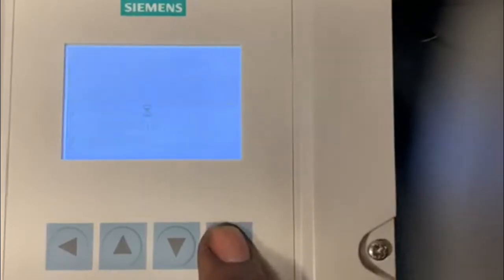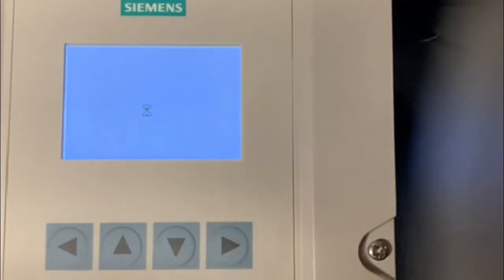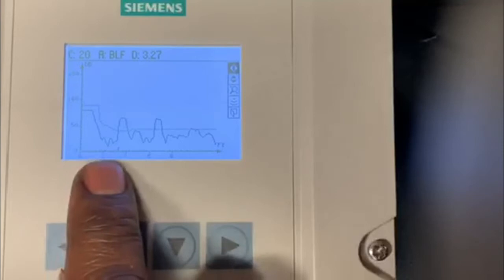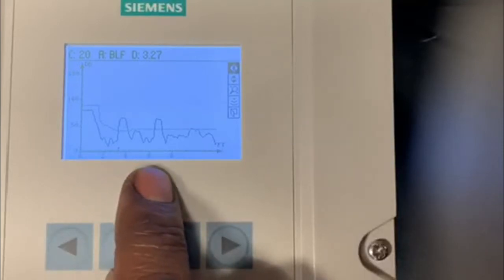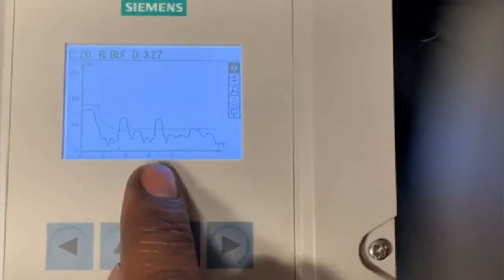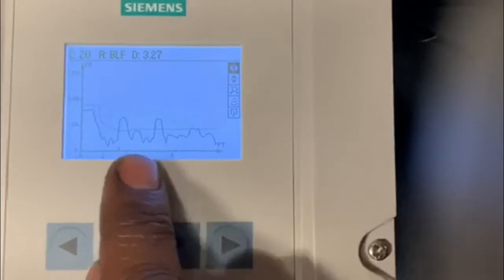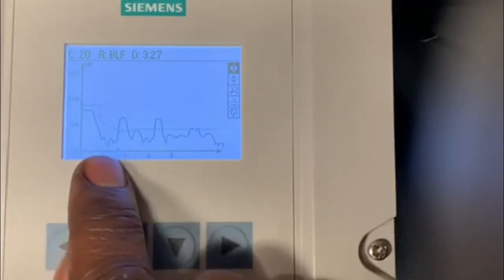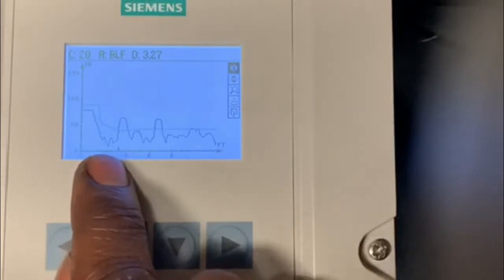So we hit the right arrow to take a look at the echoes themselves. And we notice that there are two very prominent echoes. One we know is the true level, but then there's a secondary value closer to the front. We confirmed this earlier: it was an obstruction. There are a few ways to omit this obstruction from our calculations.